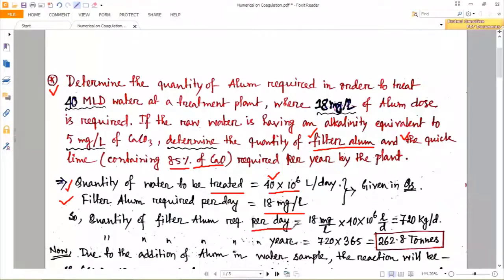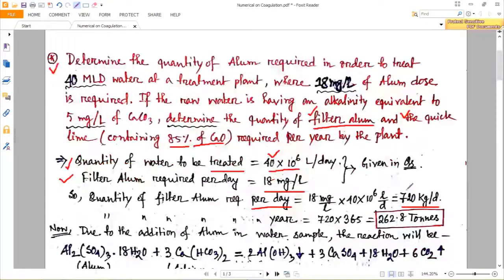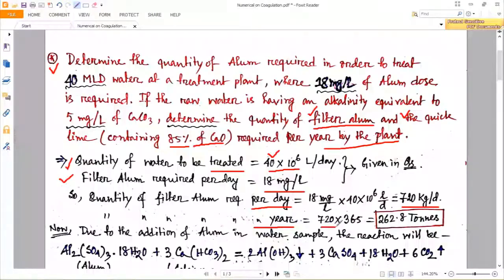Per day requirement of filter alum is 18 multiplied by 40 multiplied by 10⁶, which comes to 720 kg per day. Since the question asks for the amount required per year by the plant, this value should be multiplied by 365. So 720 multiplied by 365, converting into tons, gives 262.8 tons per year.